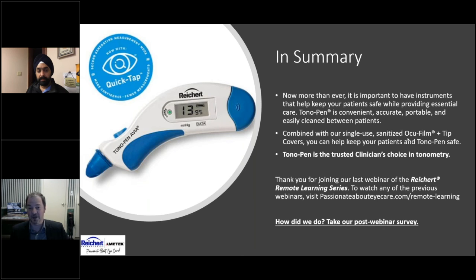But that being said, this product does not require high-level disinfection because nothing reusable touches the cornea. That's the magic of the disposable tip cover. You only need to wipe down the body of the instrument with something like a PDI or an isopropyl wipe after you've used it. So I think we have another couple questions that came in.